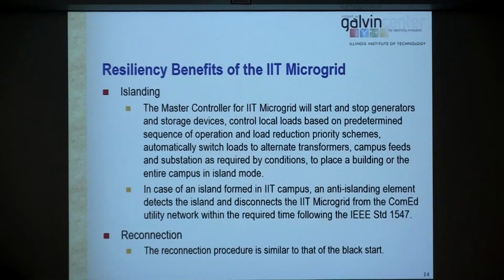So if right now, at this moment, we need to create an island on the campus, we identify how much load we have, and then we put the campus into one of those 6 modes of operation in order to keep the lights on. After that, we do the reconnection when the system is back to normal, and then we operate the system.